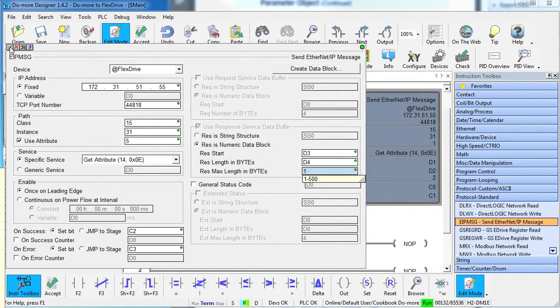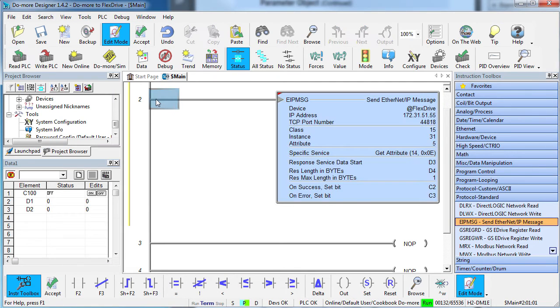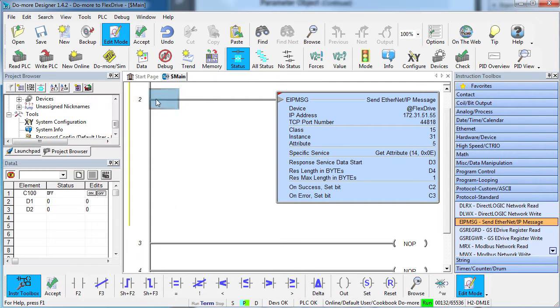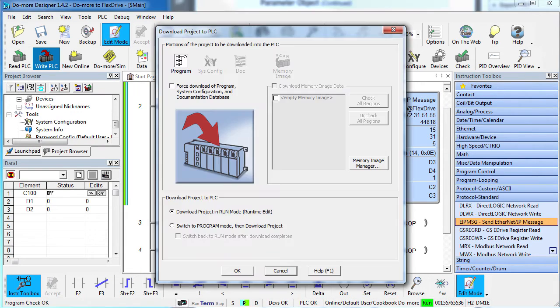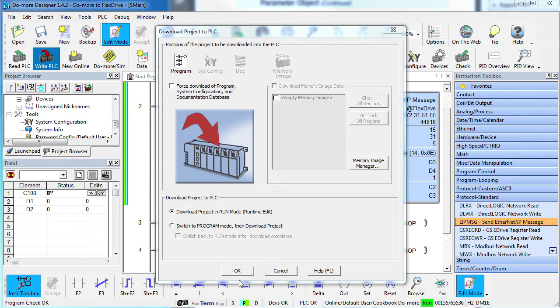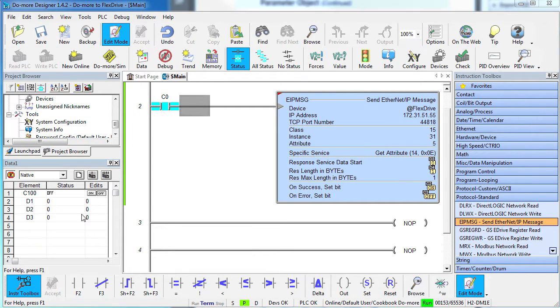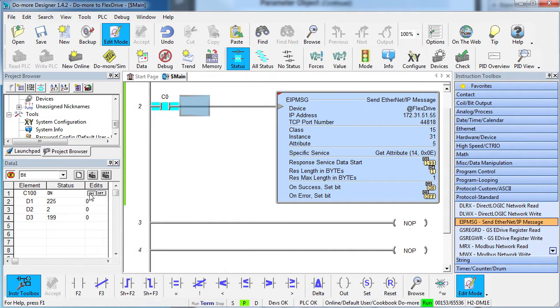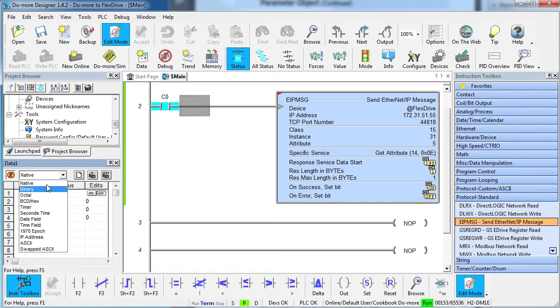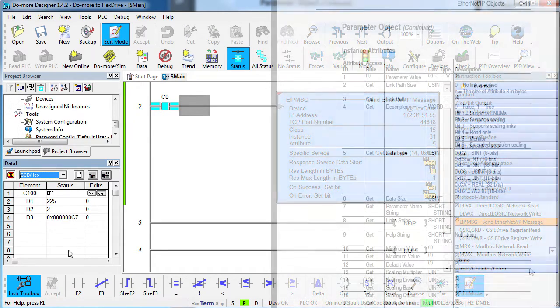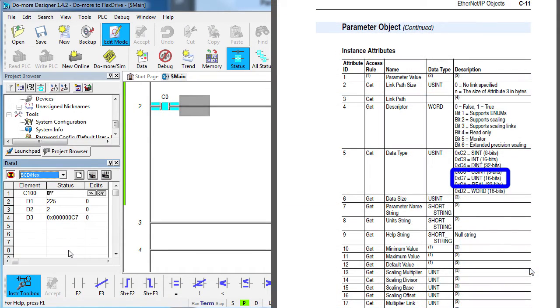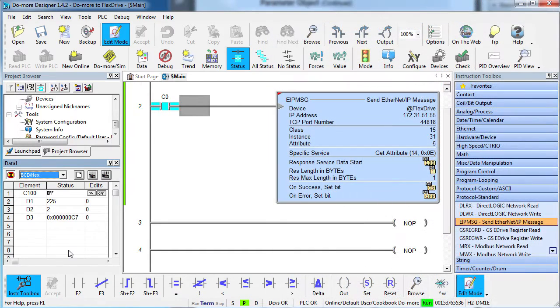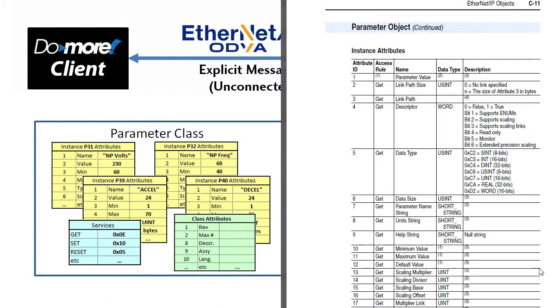Let's trigger this instruction on the success of the previous one. And write it out to the DoMore. And over in the data view let's add our new results. Toggle the control bit and sure enough, the device tells us the data type for parameter 31 is 199 which is C7 hex which according to our lookup table is unsigned 16-bit. So before I started this video, I executed this command so I would know what data type to use for that first example we did. Again, everything you need to know is in these tables and once you understand how to use them, you will be in total control of your device.